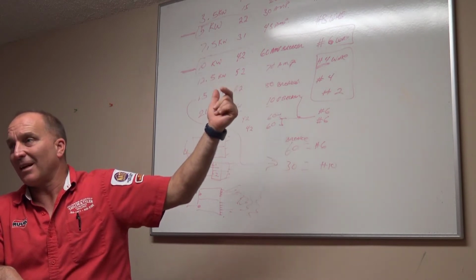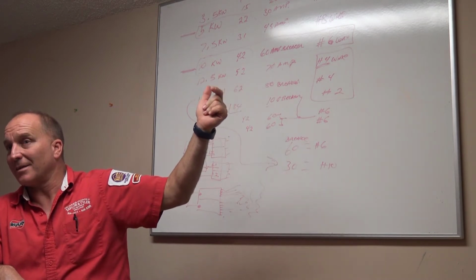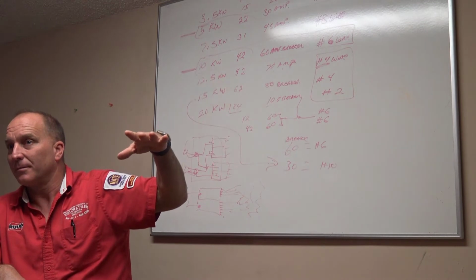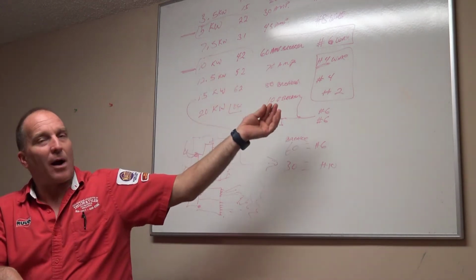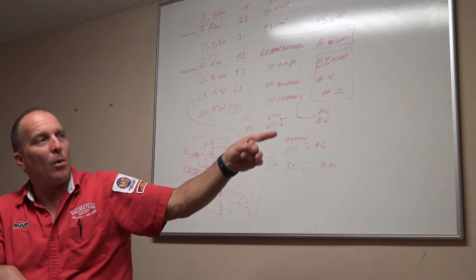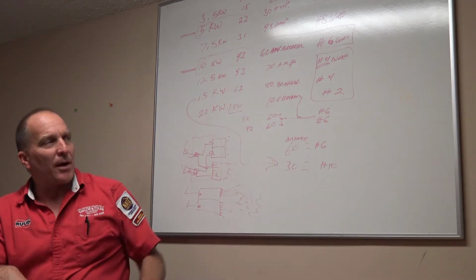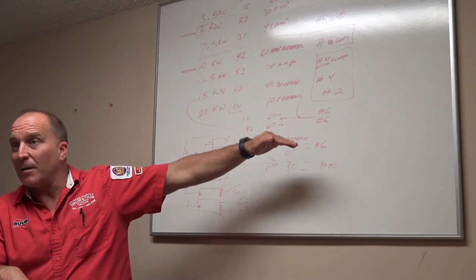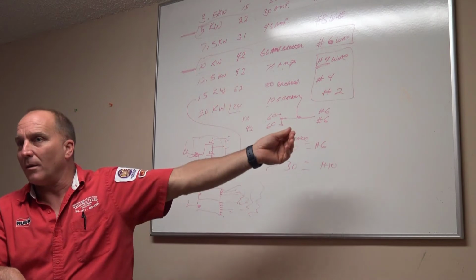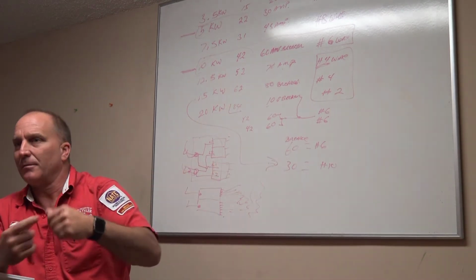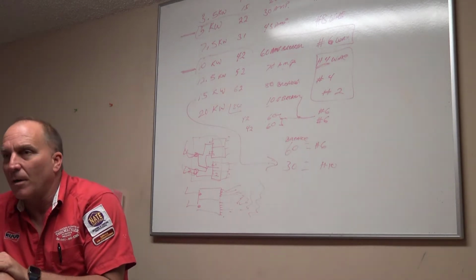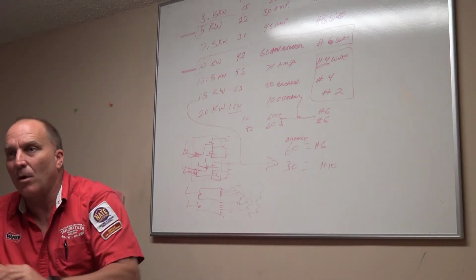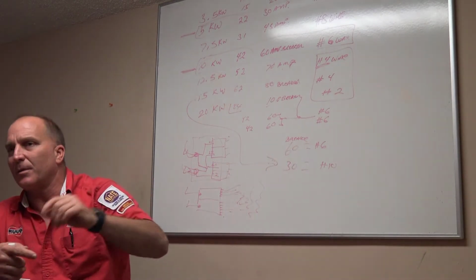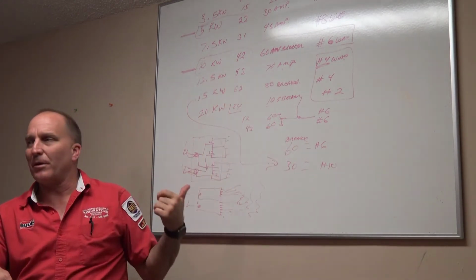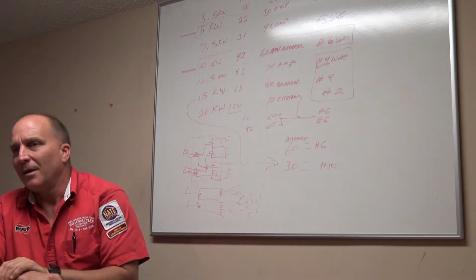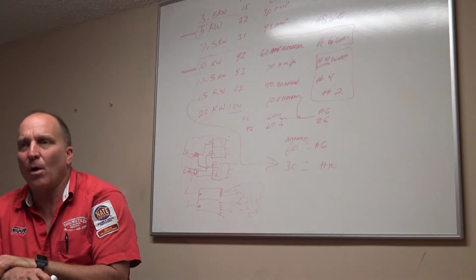Yeah. I've disconnected my 5 kW heat, but I have to make sure that I disconnected the 5 kW heat on the correct heating element. Right? I could literally pull that wire off of the breaker, and if I follow L1 around and I go, oh, okay, on this breaker right here, I see I have a blower motor to it and I have a 5 kW to it. If I literally pull L1 off of that breaker and I put some black tape on it, can't touch anything now, can that L1 ever come on? Or can that last heating element ever come on? And I pull the yellow wire off of it too, and I tape it up because the L1 goes around through it, comes back to L2 on my yellow, right? And I tape it up as well too. Can that heat strip ever get power and ever run? The answer is no.